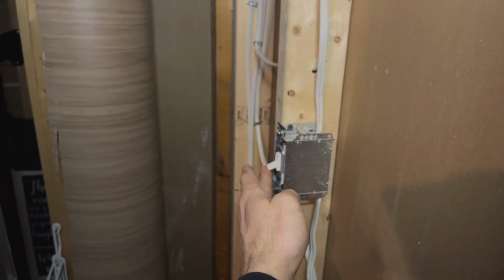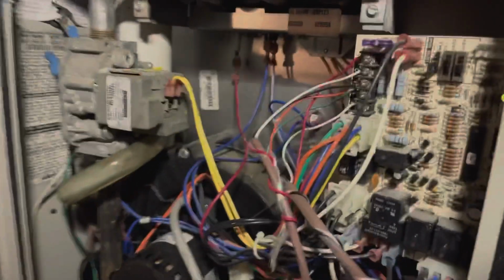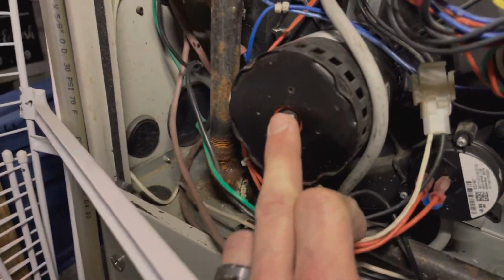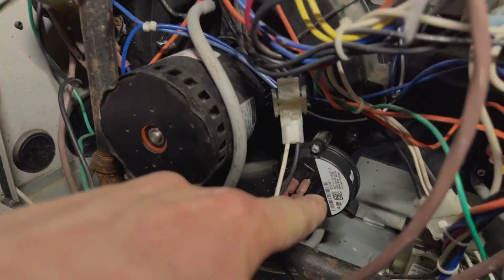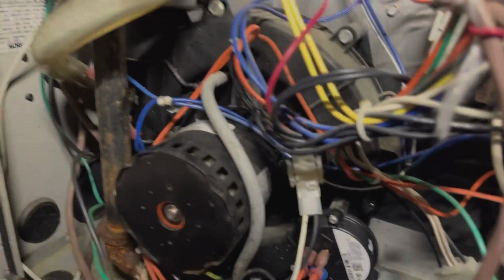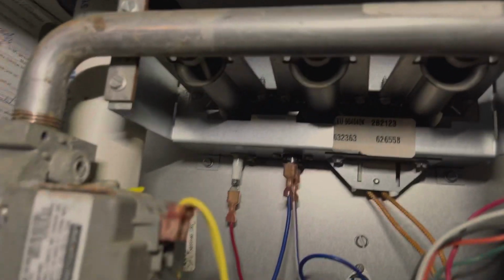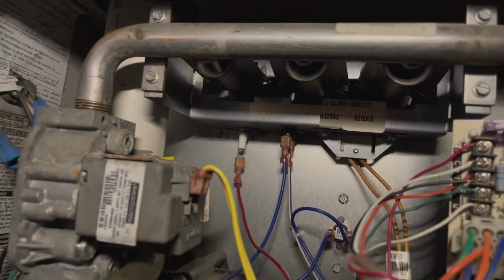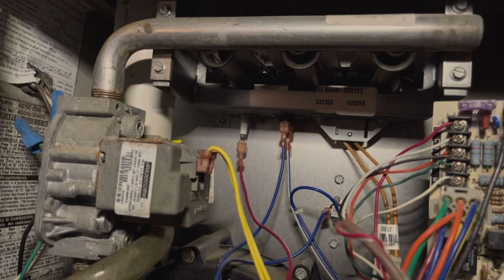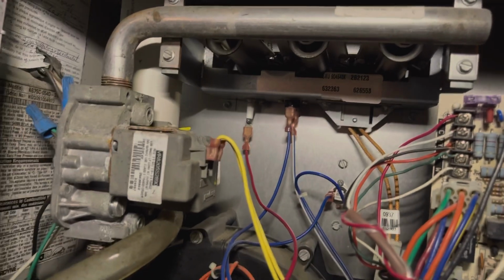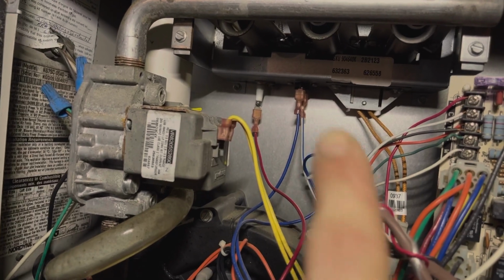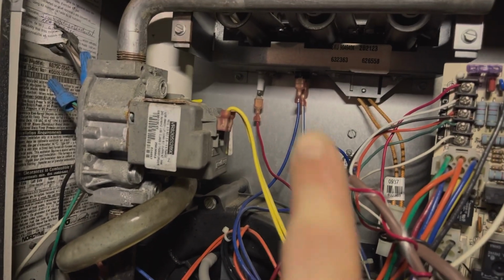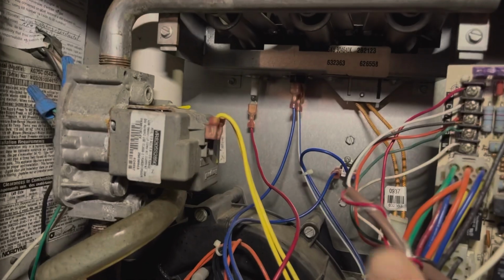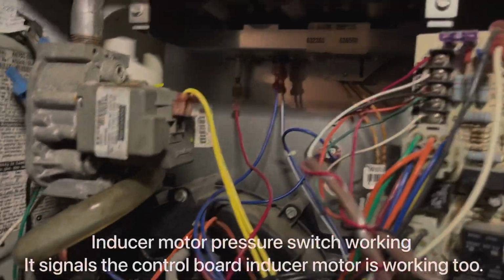Okay, I'm going to turn it on and run over quick. Thermostat clicked, called for heat. No lights flashing yet. Inducer motor is going. Pressure switch is sensing the pressure is going for the inducer motor. Then we should see this glowing up here, and then the gas should come on. Now, if any of the other limit switches weren't working properly, they would have already tripped because they're in series. So if this goes, we know the limit switches are good.